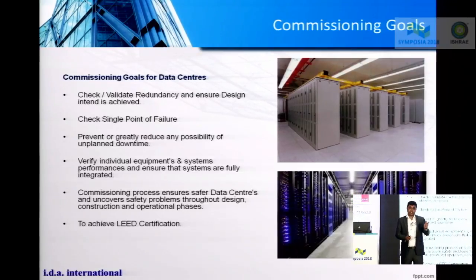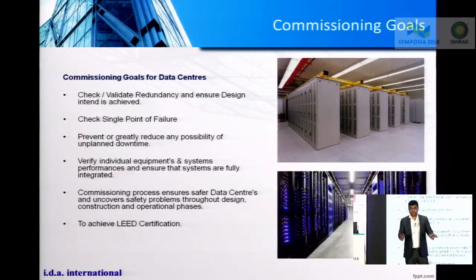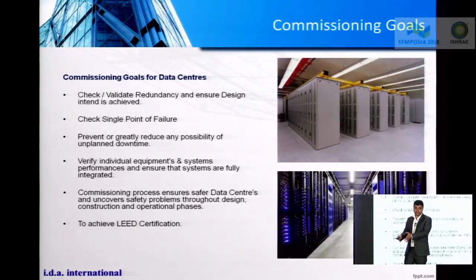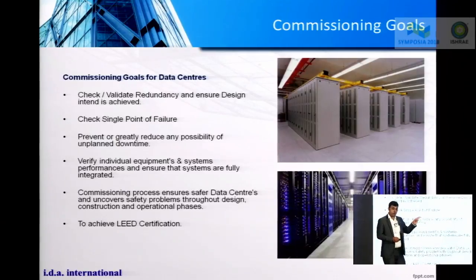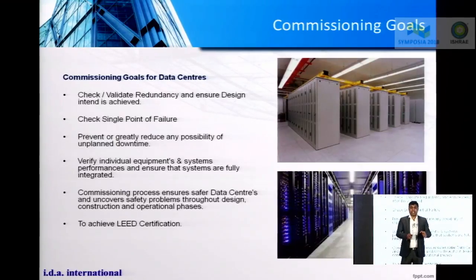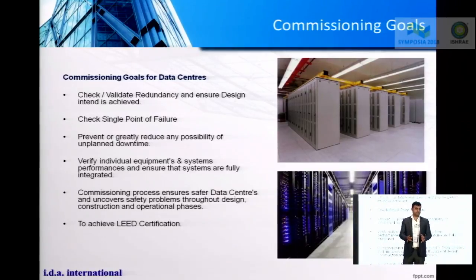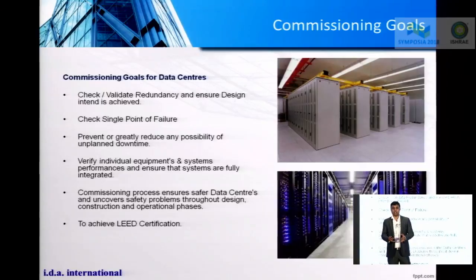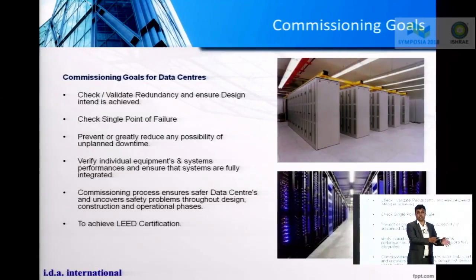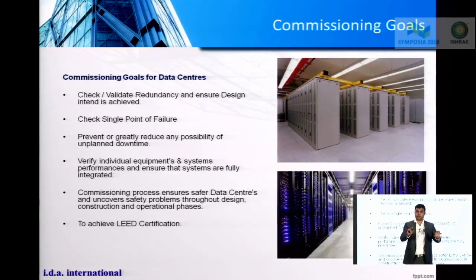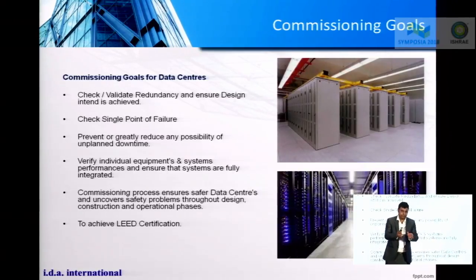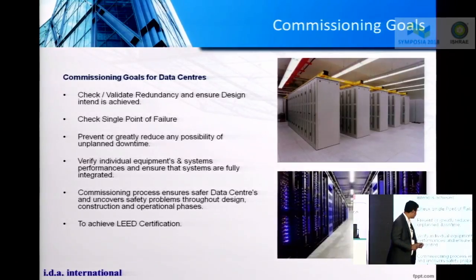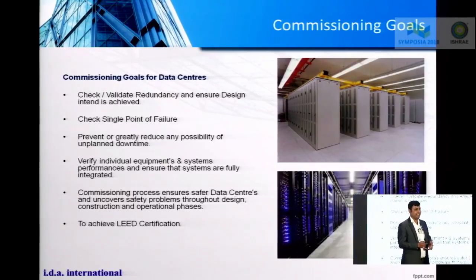The second goal of commissioning is to ensure there is absolutely no single point of failure, not just on paper, but practically on site. The third and most important goal of commissioning is that it ensures or greatly prevents any unplanned shutdowns. Now, think of a situation where you have a fault in the system and you are not able to identify that fault during the project stage. It is important not just during projects, but during operation as well, because you're following a very standard process for commissioning, which ensures that every single step that you take during construction is safe and prevents any hazard. And finally, the last goal is to achieve LEED credits.